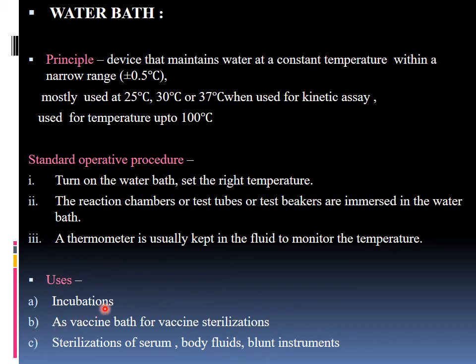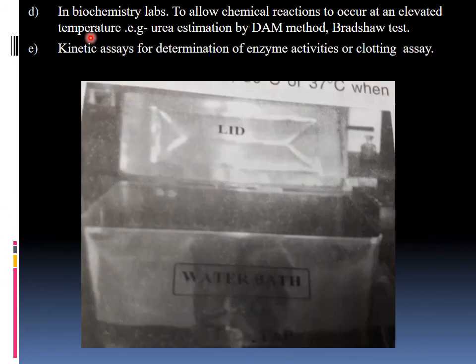And uses is mainly for incubations, as a vaccine bath for vaccine sterilizations, sterilizations of serum, body fluids, blunt instruments. Also in biochemistry labs, to allow chemical reactions to occur at an elevated temperature, like in urea estimation by Dam method or Bradshaw test. In kinetic assays for determination of enzyme activities or clotting assays, if you want to see some enzyme activities, say SGOT, SGPT or ALP, then also we may use it.